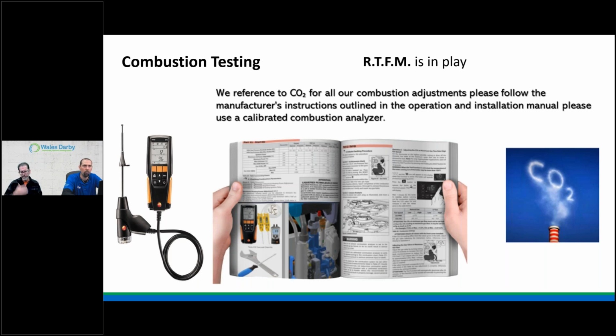So every manufacturer has their manual based on that particular model or that series. They'll show you what you need to set the gas valve up to, the firing rate and all that good stuff. So this is really something that I hope you have one. It is calibrated, right? It needs to be calibrated, and you understand what you're trying to achieve here, all right?